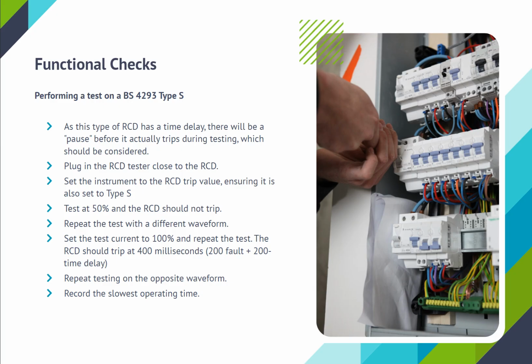Repeat the test with a different waveform. Set the test current to 100% and repeat the test. The RCD should trip at 400 milliseconds, 200 fault plus 200 time delay. Repeat testing on the opposite waveform. Record the slowest operating time.